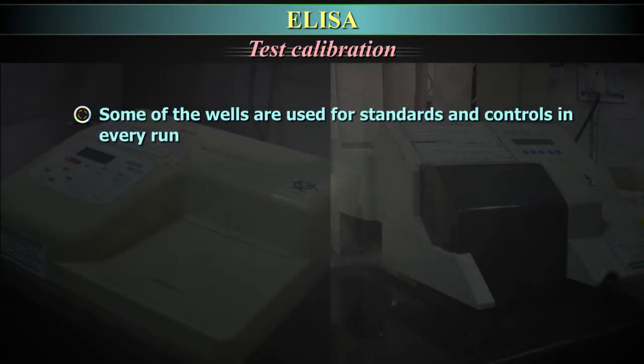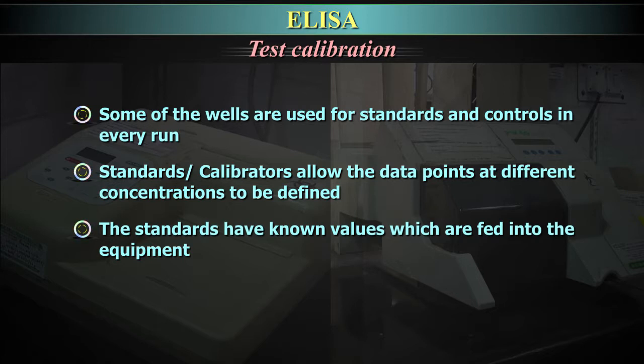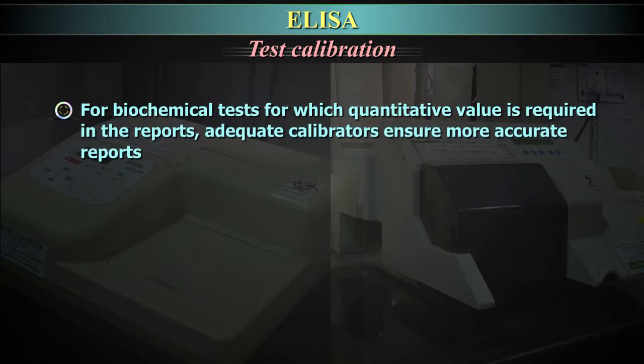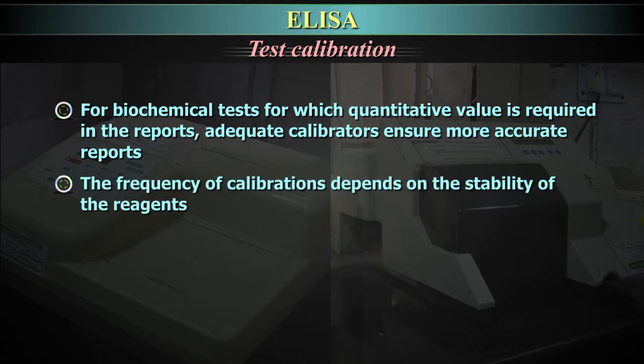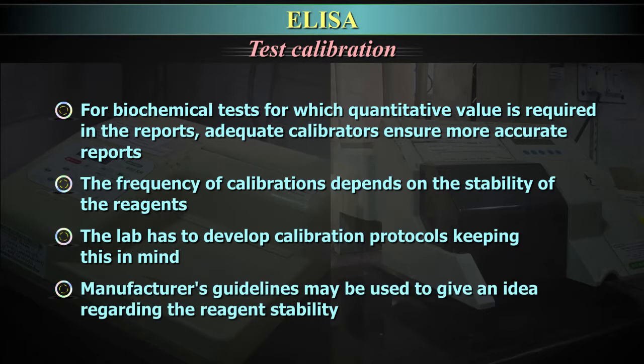Test calibration. Some of the wells are used for standards and controls in every run. Standards or calibrators allow the data points at different concentrations to be defined. The standards have known values which are fed into the equipment, and the equipment uses the data from these calibrators to plot the curves. For biochemical tests for which quantitative value is required in the reports, adequate calibrators ensure more accurate reports. The frequency of calibrations depends on the stability of the reagents. The lab has to develop calibration protocols keeping this in mind. Manufacturers' guidelines may be used to give an idea regarding the reagent stability.